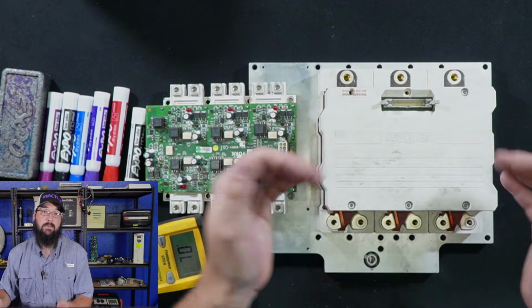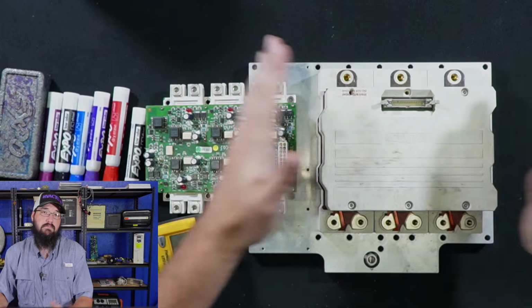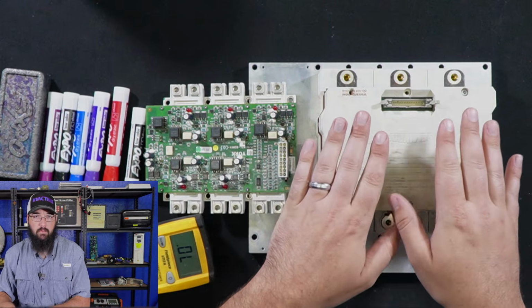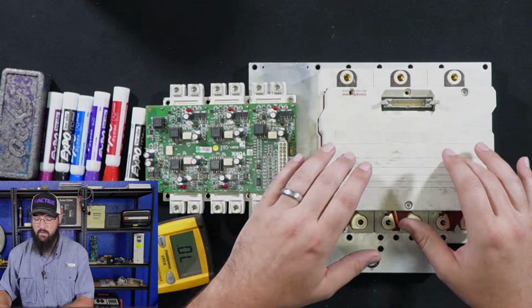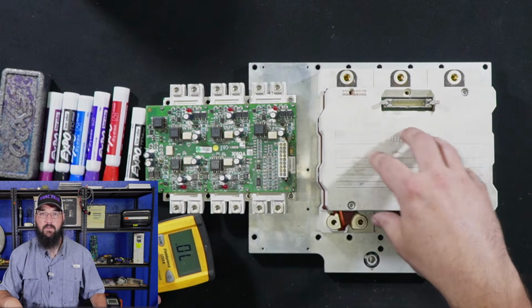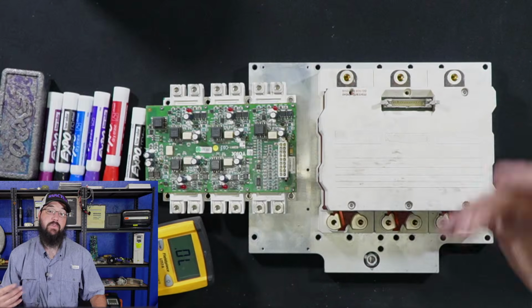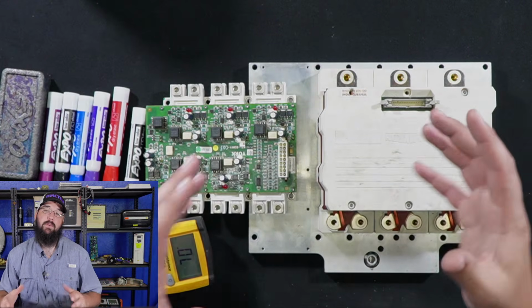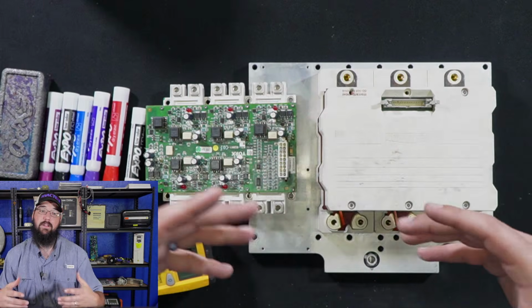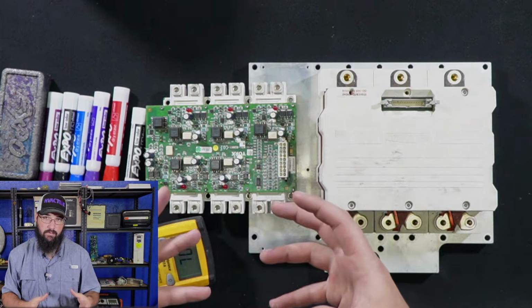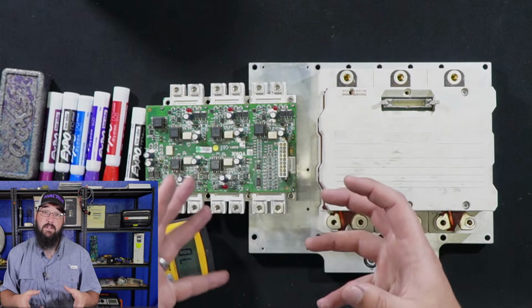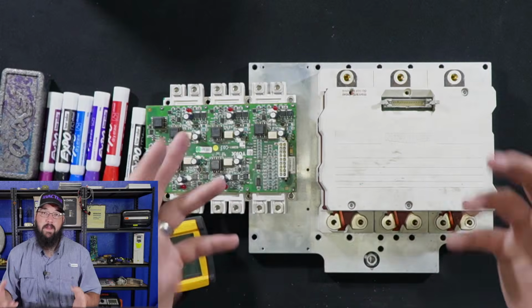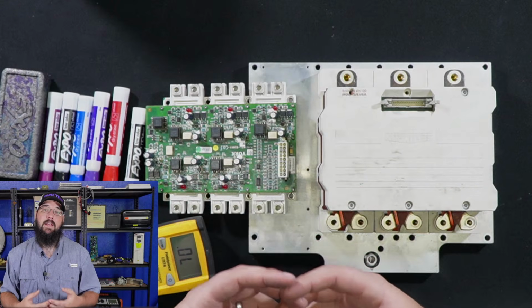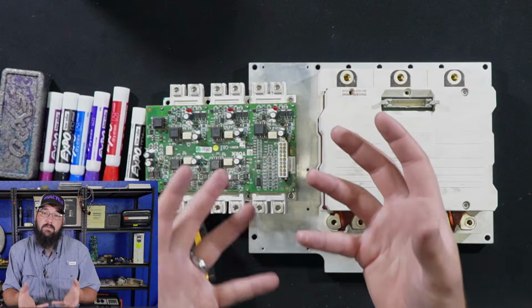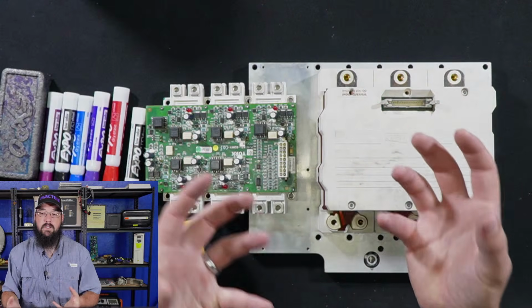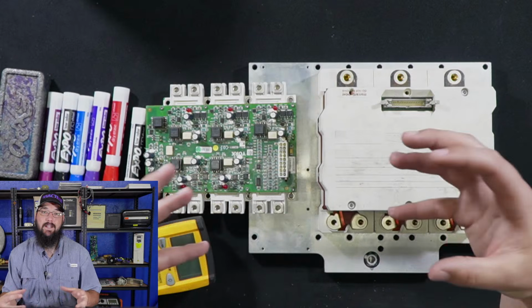If we're not having any symptoms, awesome. But I wouldn't be shocked if I was having symptoms, at least occasionally. Which, keep in mind, an inverter on a Turbocor with a mag bearing, inverter issues can present as bearing faults, because part of what will happen when these inverters begin to fail, they don't control the magnetic field properly, and that causes instability in the rotor. Well, the sensors on a mag bearing are going to sense that instability as a bearing issue, because the bearings are having trouble controlling that now.